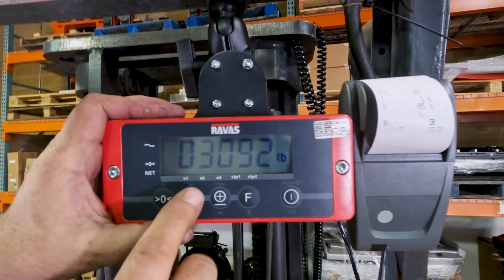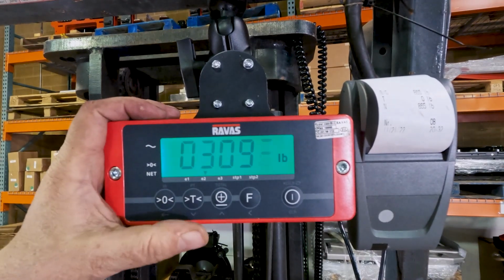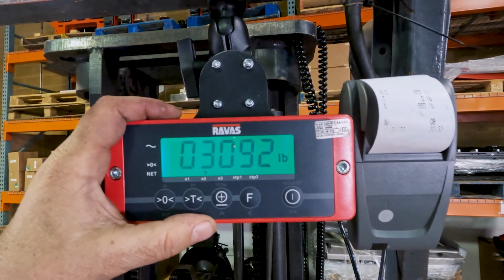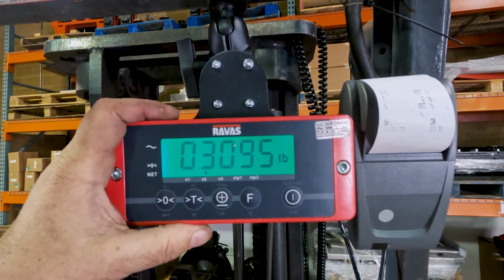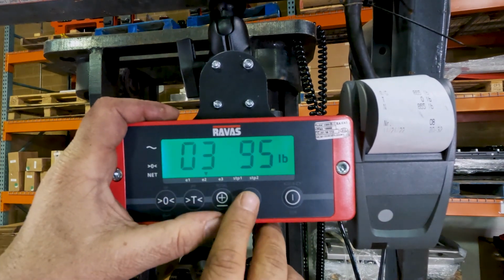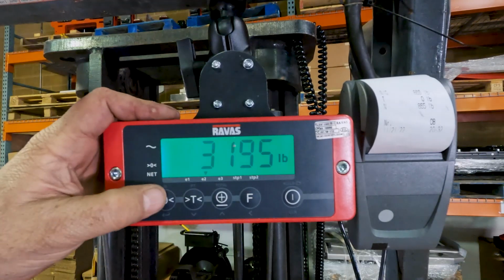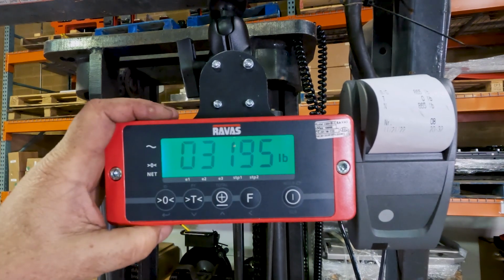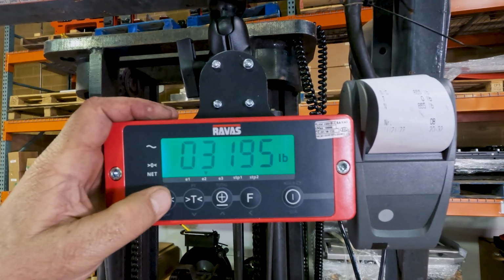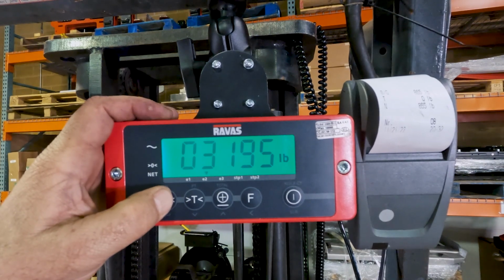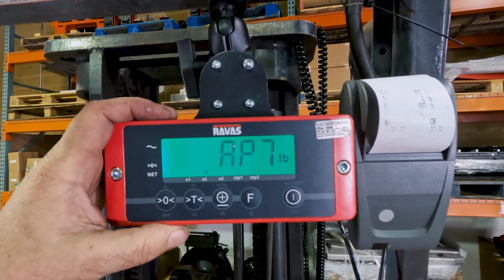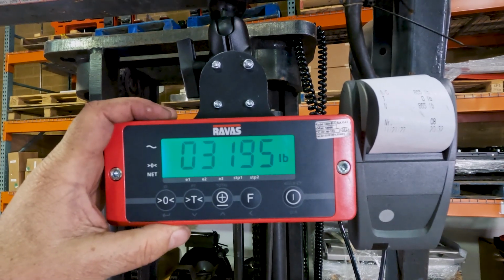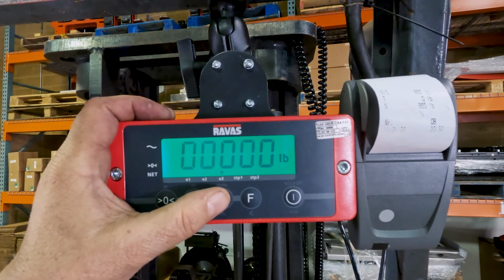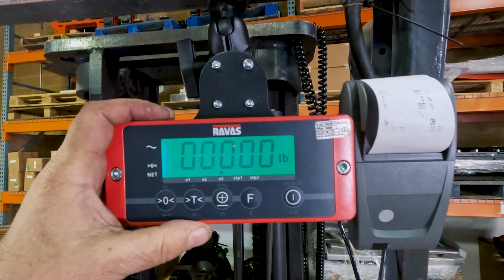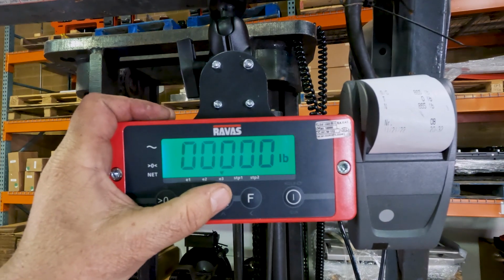we are now going to, with E2 flashing, hit the enter button. Here we are going to tell it what our new weight is. We're going to hit the enter button. E2 is now flashing. We are going to press and hold until it says adjust. Release, and let it count down. We're going to hit the up arrow one more time. Then since we're only doing 2 weights, we're going to hit the up arrow a third time.